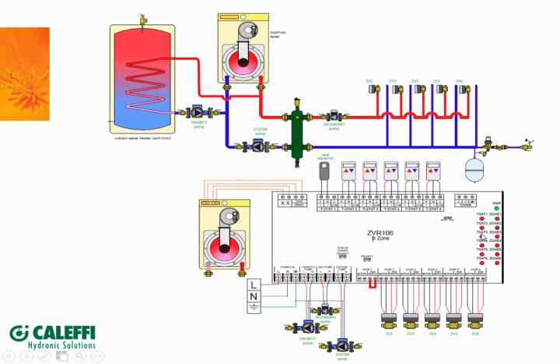Space heating is, just as we said, if you get a call for heat, it will turn on that LED. It'll send 24 volts to the corresponding motor. Once the end switch is closed, the other LED lights up. The system pump and the secondary pump would turn on, and the XX contacts would close, delivering heat out to that zone. If the aquastat calls, it will drop power to any of these zones.